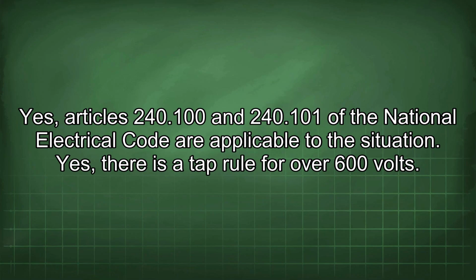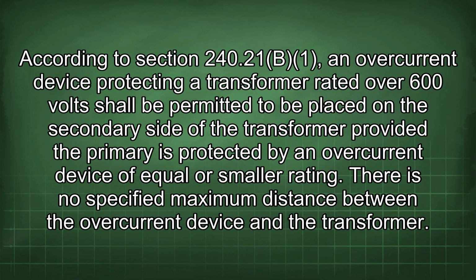Yes, Articles 240.100 and 240.101 of the National Electrical Code are applicable to the situation. Yes, there is a tap rule for over 600 volts. According to Section 240.21(B), an overcurrent device protecting a transformer rated over 600 volts shall be permitted to be placed on the secondary side of the transformer provided the primary is protected by an overcurrent device of equal or smaller rating. There is no specified maximum distance between the overcurrent device and the transformer.